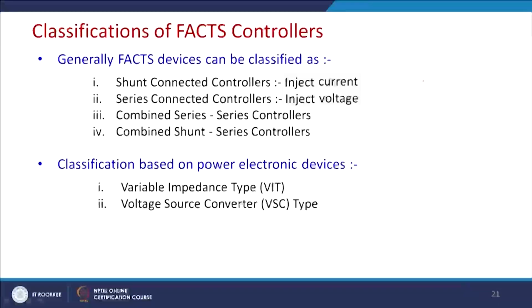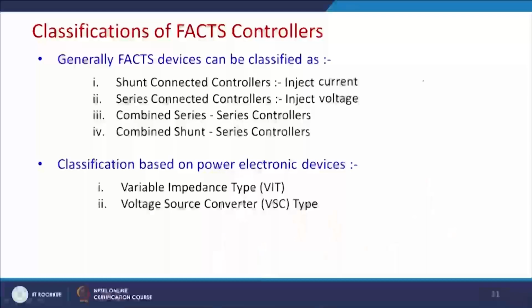Now, there are different kinds of FACTS devices. A shunt connected controller injects current, a series connected controller injects voltage, then there are combined series controllers and combined shunt series controllers. Another type basically injects impedance; these are called variable impedance type, VIT, and another type is the voltage source converter.